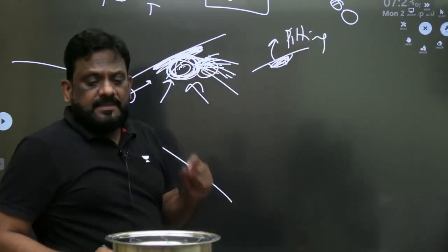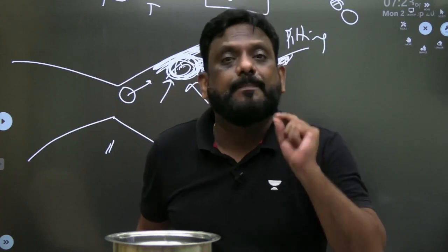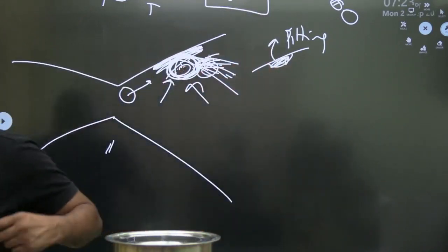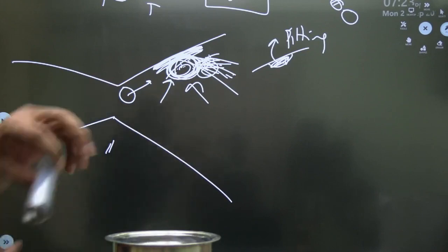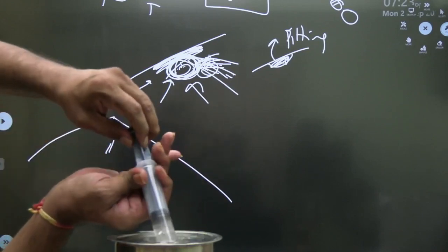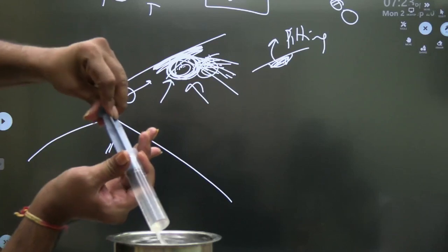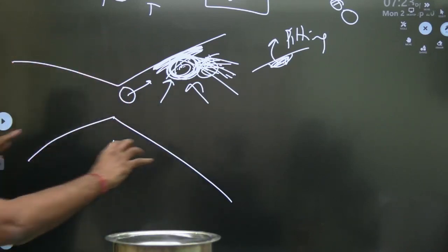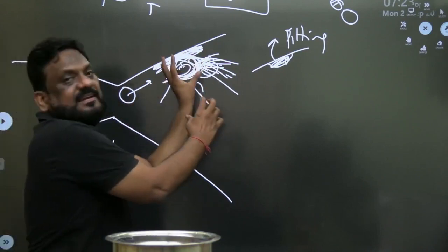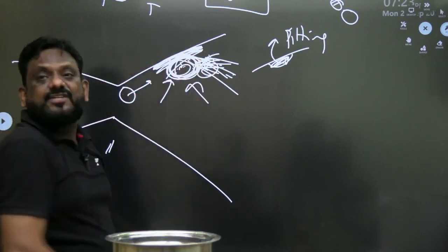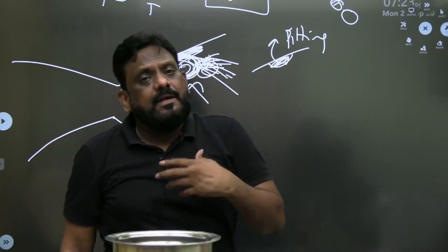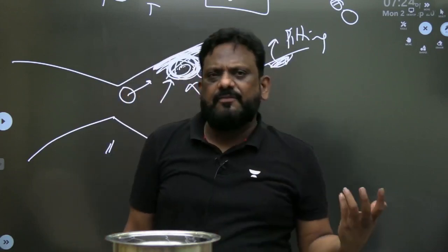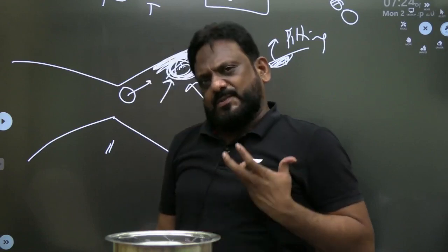So therefore, cavitation is a low vapor pressure, low pressure phenomenon. Because when the pressure is less than vapor pressure, you see, I'm sucking the fluid, I'm creating low pressure. Look here, when the pressure is low, you can see clearly, and these bubbles, when they are carried to high pressure, due to implosion, severe pressure pulses are created, and thereby it may cause damage. And if you want a detailed analysis, I explained what is evaporation, what is boiling, all this very clearly.